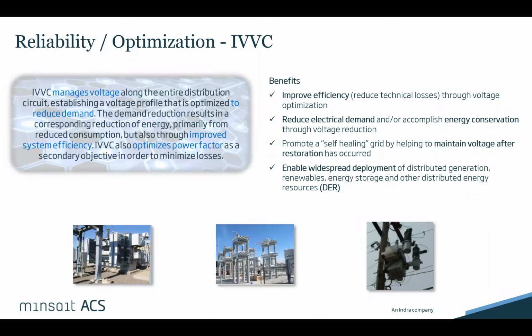And then secondary to FLISR probably is integrated volt VAR control. Some might refer to it as volt VAR optimization. But again, improving the efficiency through voltage optimization on the network, reducing the demand and/or energy, depending on the objectives of the utility. And of course, used in concert with FLISR, it can continue to optimize the grid, even when the network is in an abnormal state, whether that be as a result of a fault restoration or seasonal switching. And then, of course, IVVC can also help enable the widespread deployment of DER on the distribution network by helping to manage in an integrated fashion any voltage issues which might be presented as a result of that deployment.